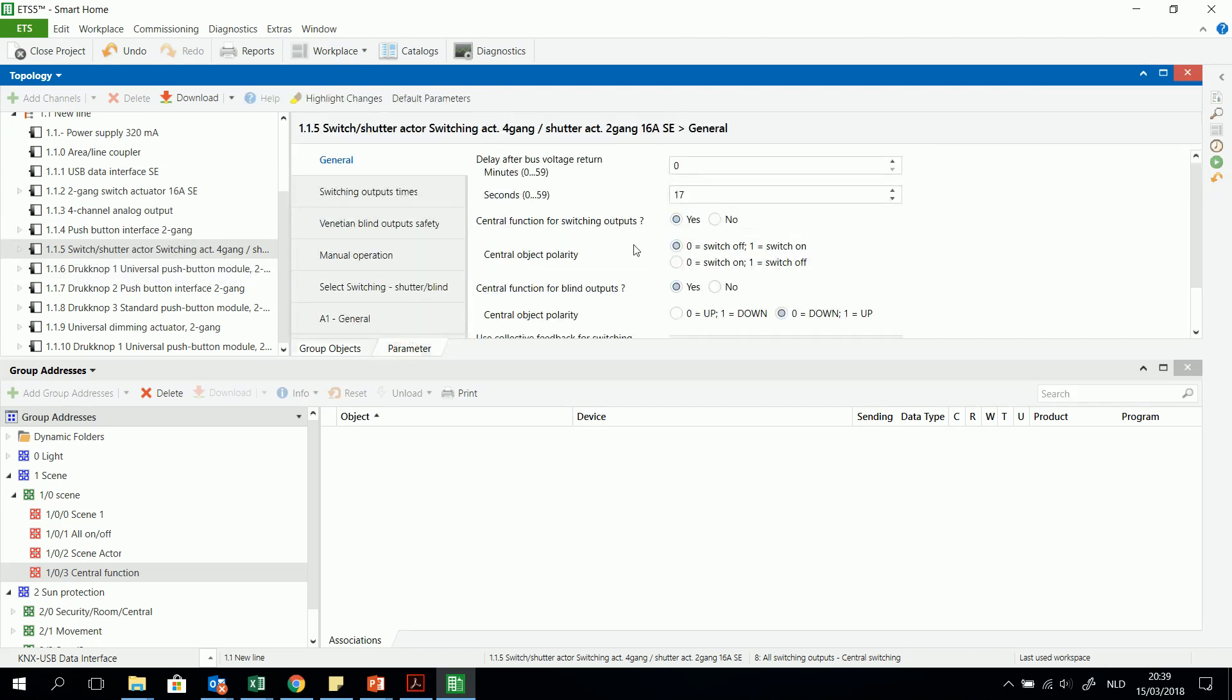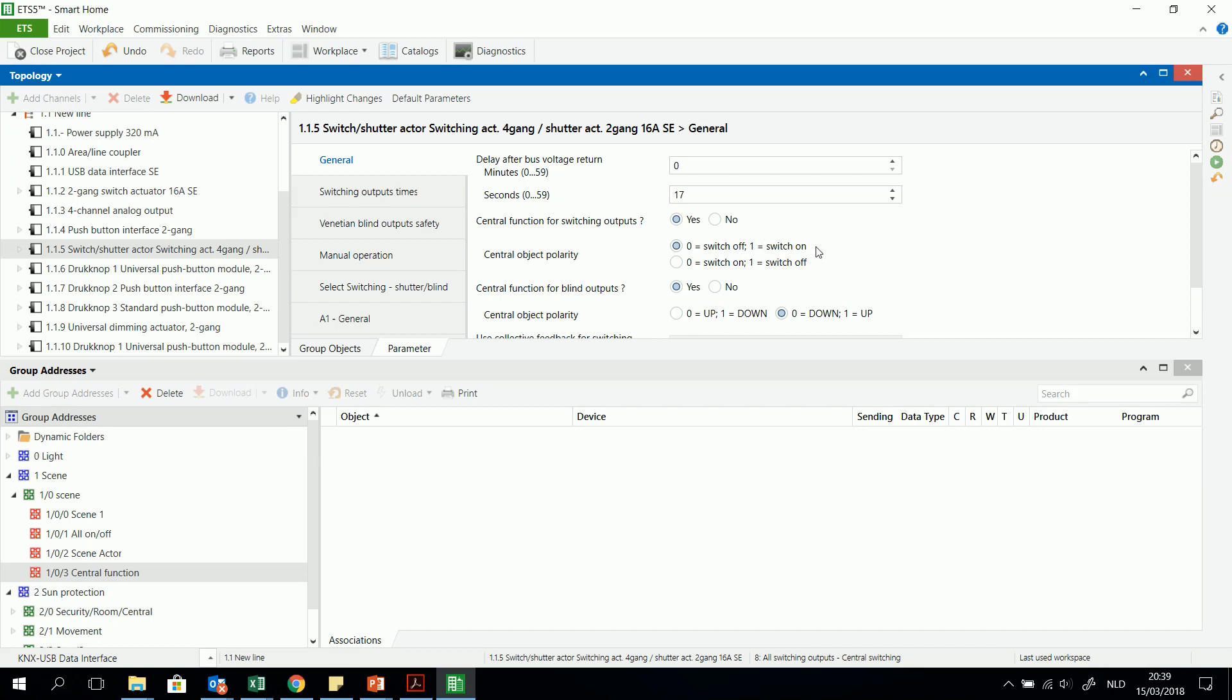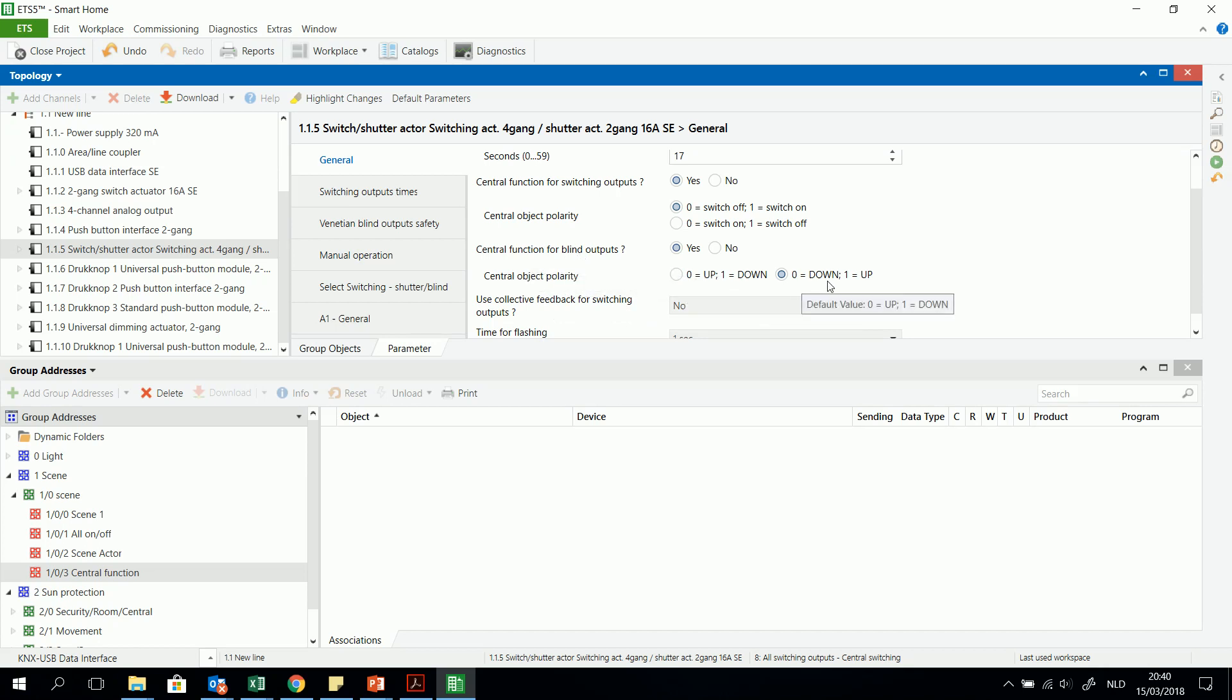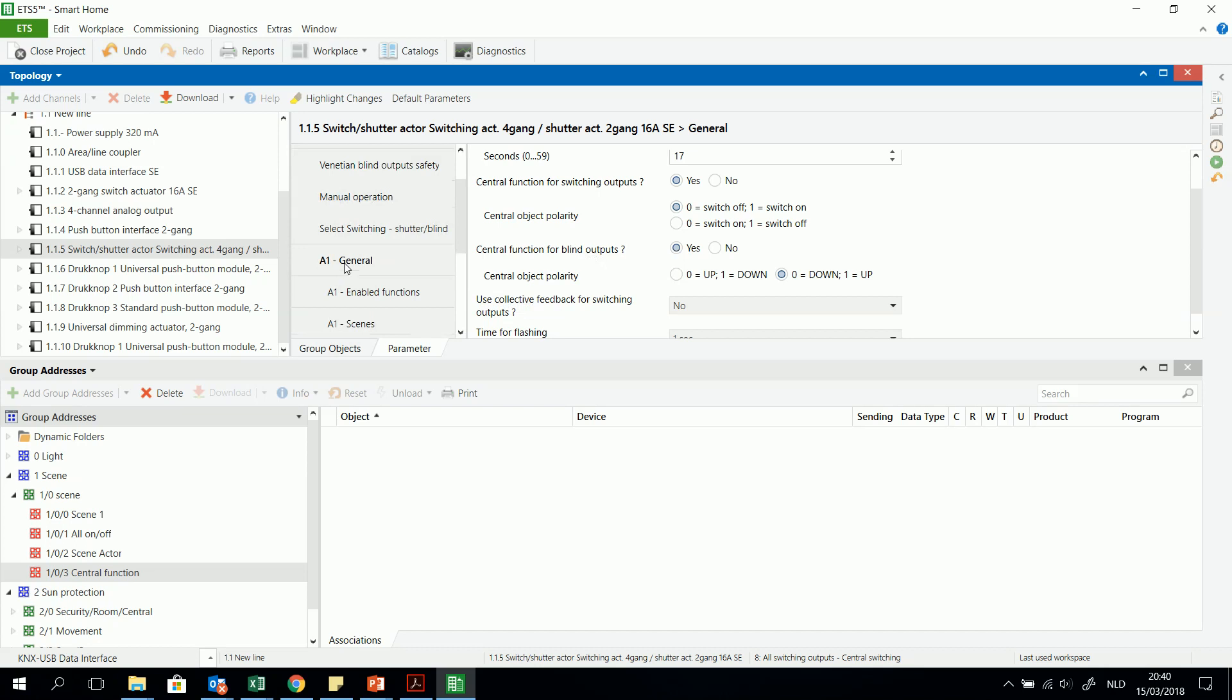So then I have to choose what is the reaction of the outputs when I send for example zero to that object. Then it will switch off. When I send a one then it will switch on the light. And the same for the blinds. I can say when I send a zero then the shutter will lower, and otherwise when I receive a one to the central object then the shutter will go up. But you can choose this. And then very important.